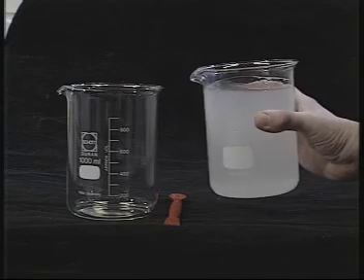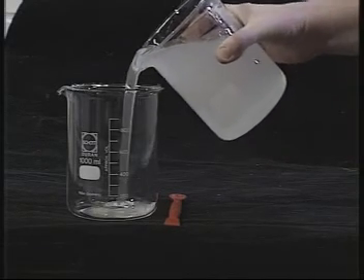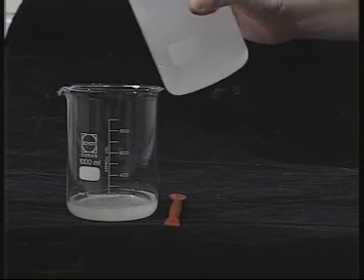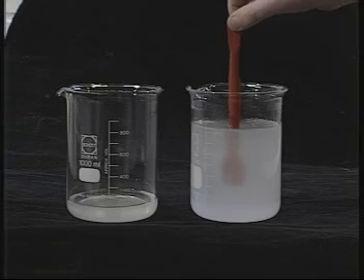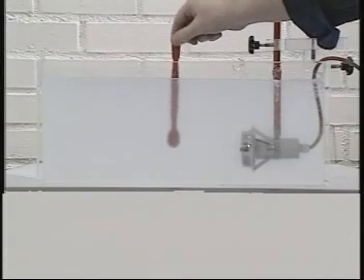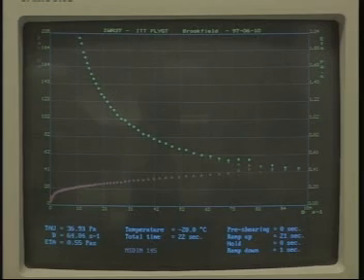Yield stress is the resistance that has to be overcome before the liquid can begin to flow. Yield stress is the main sizing variable when selecting a mixer for drilling mud. The higher the yield stress, the thicker the mud, and the more difficult it'll be to mix. So, if yield stress is higher than the value used when the application was engineered, the mixer won't be able to treat the whole load.